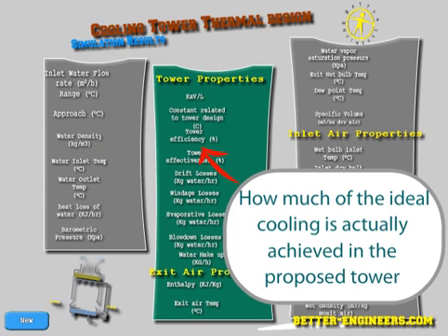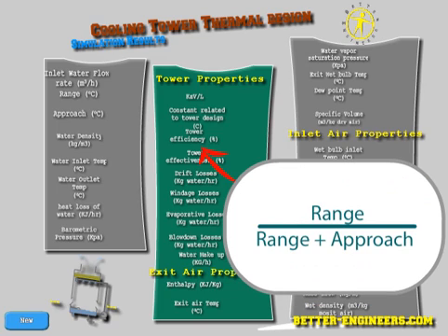Tower efficiency, expressed in percentage: in simple terms, this number tells us how much of the ideal cooling is actually achieved in the proposed tower. More technically, it is equal to the range divided by the range plus approach.